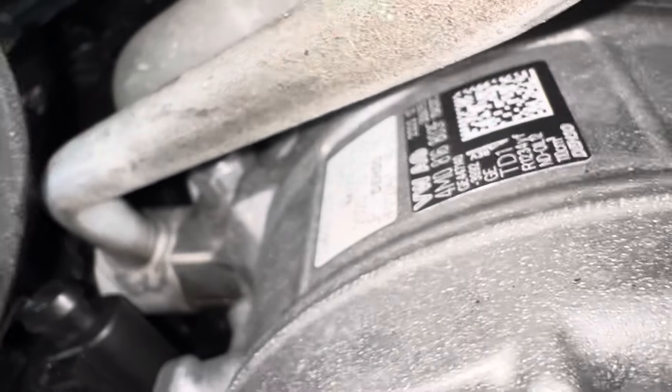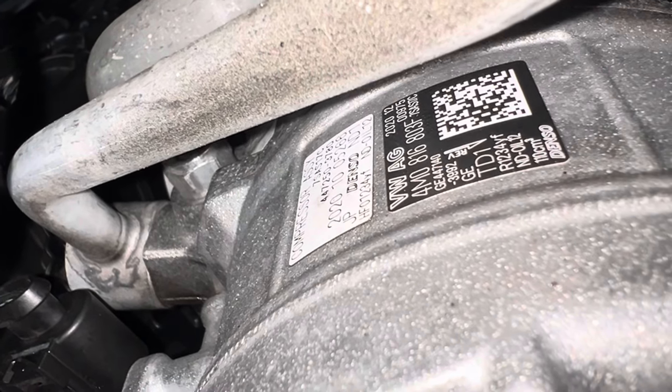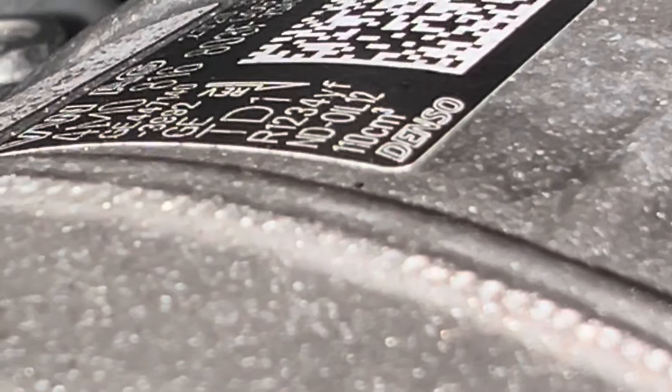Let's see if we can get closer - it's hard, I'm upside down on my back under here trying to take a look at stuff. This is not working out so well. But you get the gist of it: ND12 oil, 110 milliliters of oil.